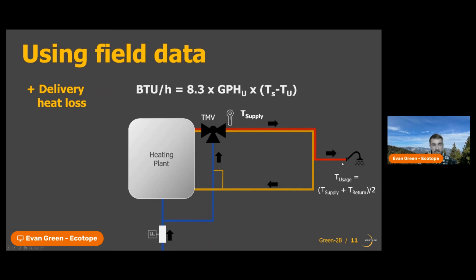And if we wanted to be really accurate about the delivery heat loss from every fixture, we would have to measure the temperature and flow at every individual fixture and then calculate the BTUs out of each fixture. And usually that's not realistic in a monitoring capacity. So we have to assume what this usage temperature will be. A high level assumption can be that this usage temperature is about halfway between the supply temperature and the return temperature. And the greater the difference you have between supply and return, the greater your error might be in making this assumption.